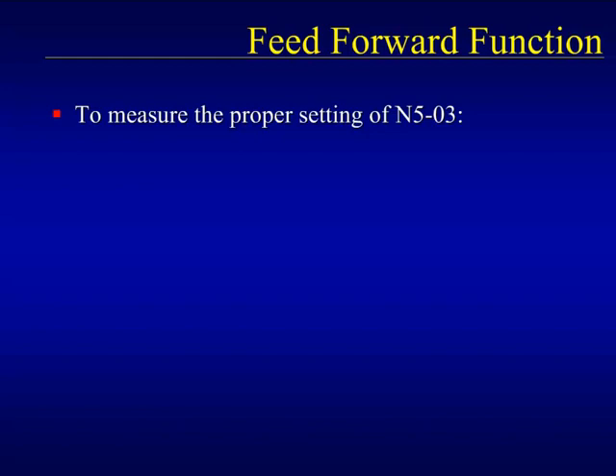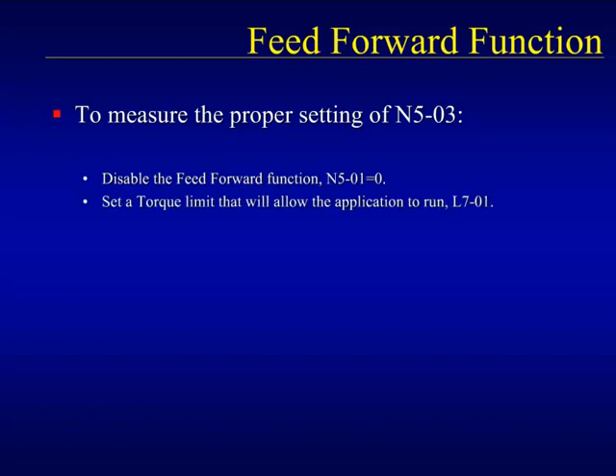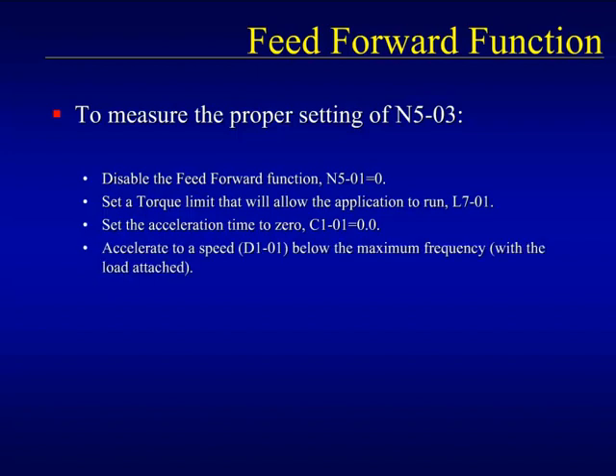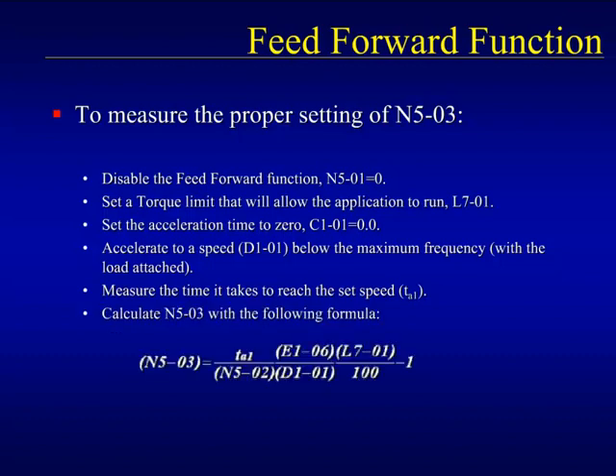To properly measure the setting of parameter N5-03, we'll take a specific test setup of the drive. Start by making sure that the feed forward function is turned off. Next, adjust the torque limit function by lowering it until it will just allow the application to fully run. Set the acceleration time to 0.0 seconds. With the full load attached, accelerate to some speed under the maximum frequency of the drive. Measure the time that it takes for the drive to reach the set speed. Use the acceleration time and the settings of the parameters to calculate the proper feed forward gain using the formula shown. Absolutely do not use this test method if the application in question is a hoist or crane type of application due to the torque limiting.